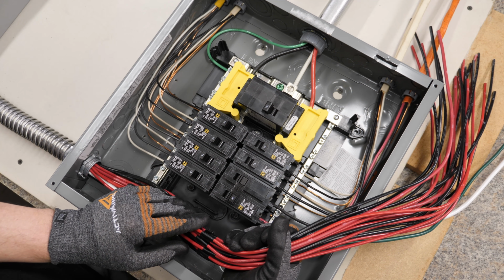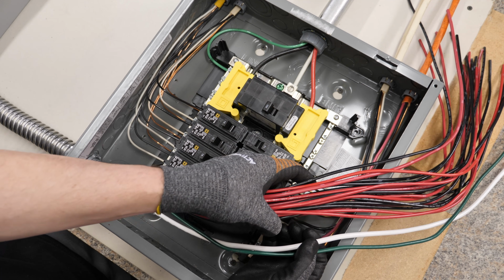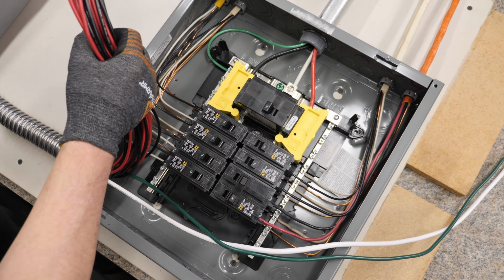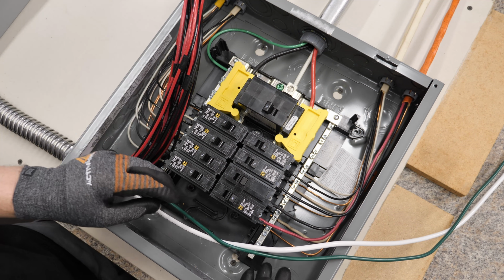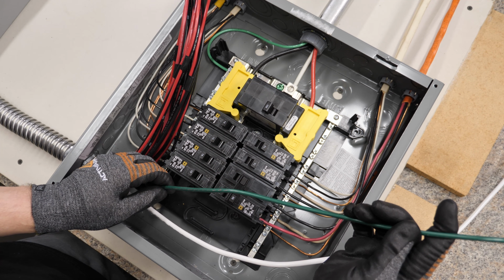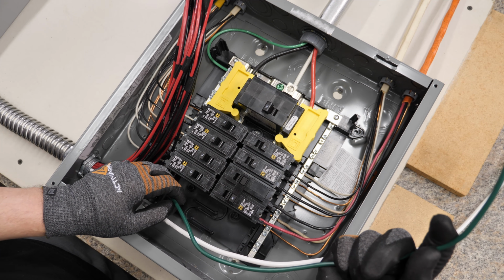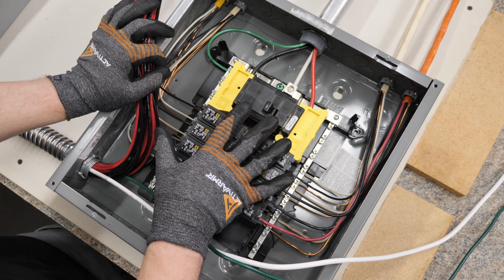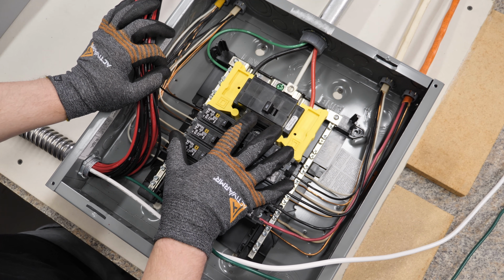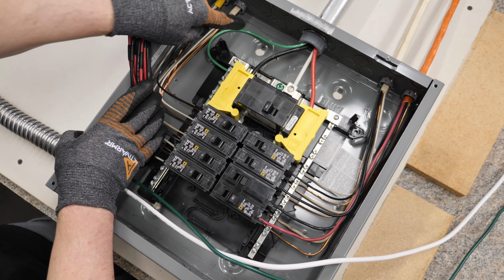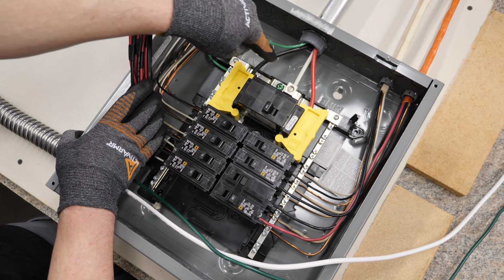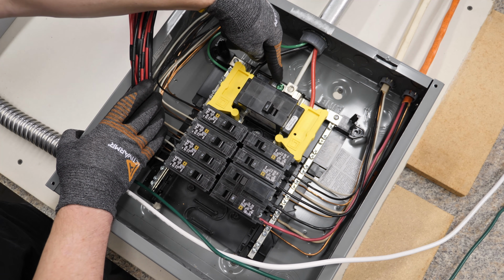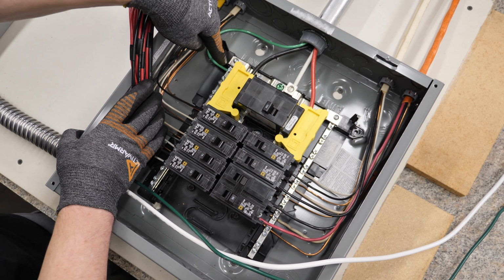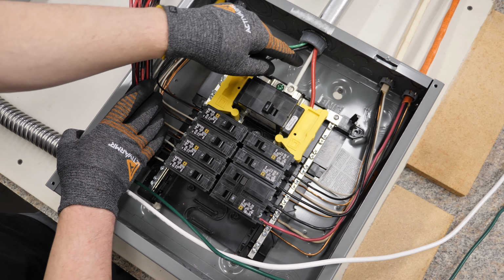First thing we're going to do is shove all the red and black wires aside, and we're only going to concentrate on the green wire first. This is your ground wire—you always want to install that first. Since this is set up in a main panel configuration, that means my ground and my neutral are bonded together. There's a green bond screw right up here which combines the ground and the neutral together.